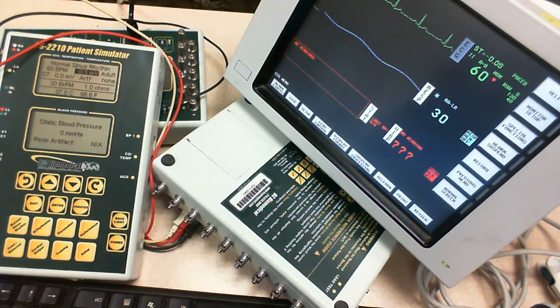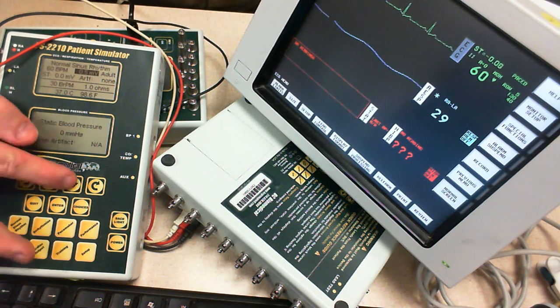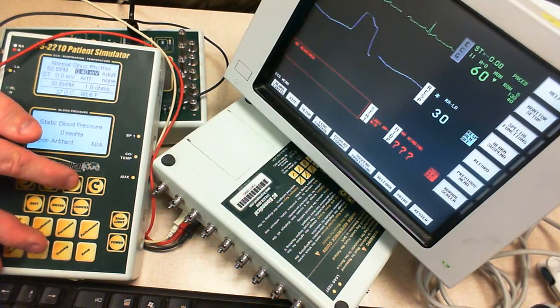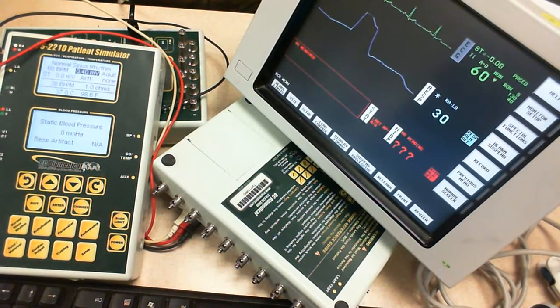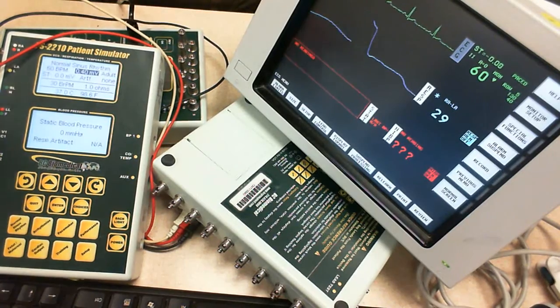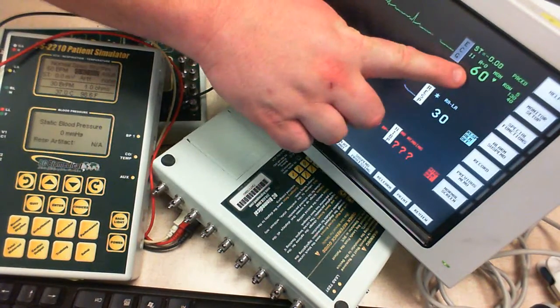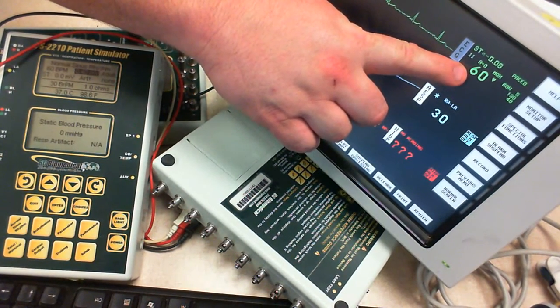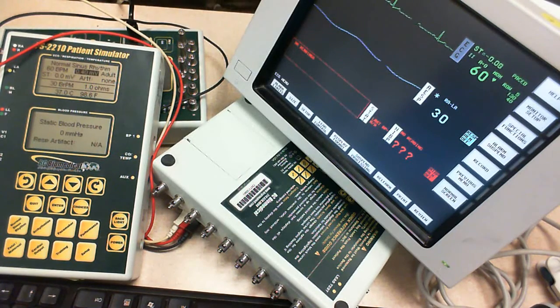There's lead 1, lead 2, lead 3. We'll talk about those in lecture. I like to do this check on lead 2. So what I'm going to do is I'm going to lower my millivolts here. And what I'm doing here is I'm looking at my heart rate count. At some point in time, my machine will not be able to count the heart rate, right?